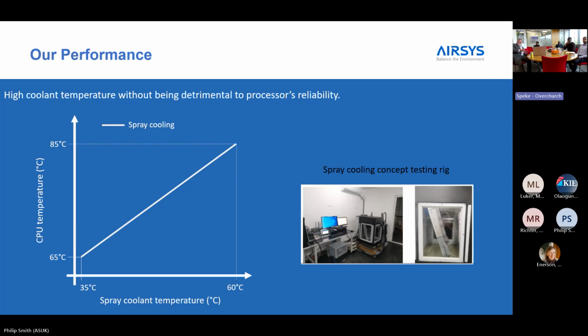So this then negates any use of refrigerant, and neither do you need to use adiabatic spraying of the dry coolers outside. They will work up to 50 degrees C before you need to enhance their performance. So anywhere in Northern Europe and even North America, they will work without refrigerant, without water. So it becomes a very efficient solution.